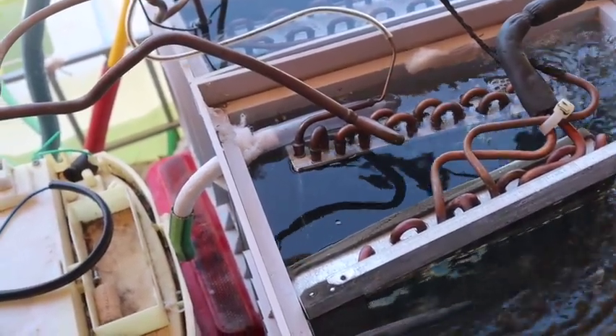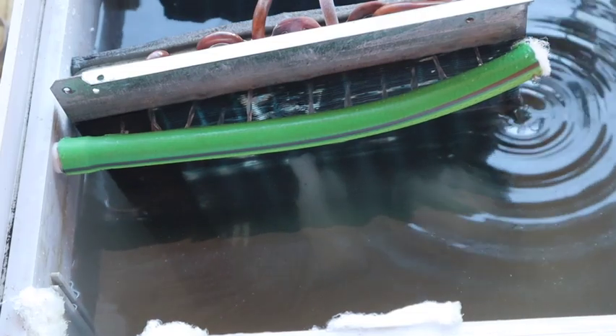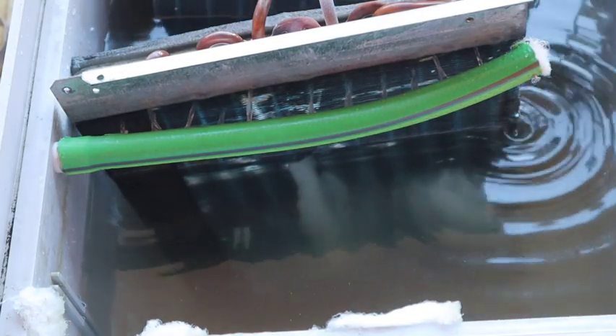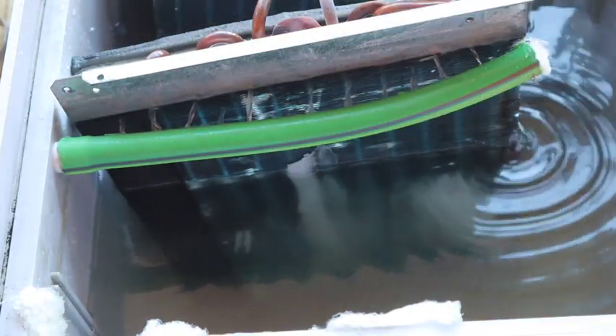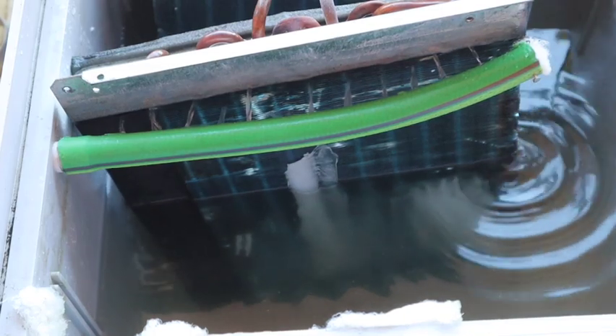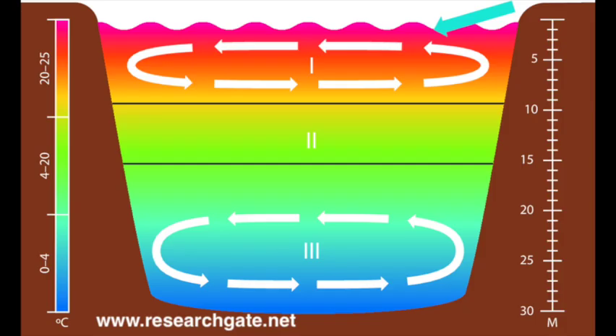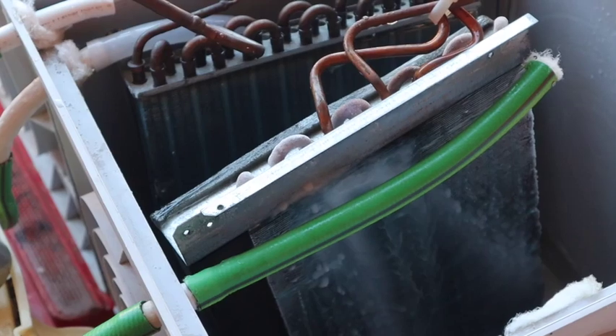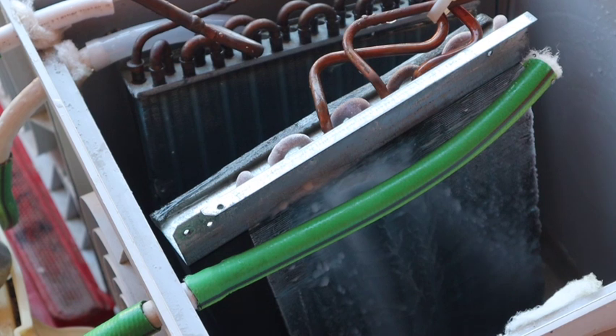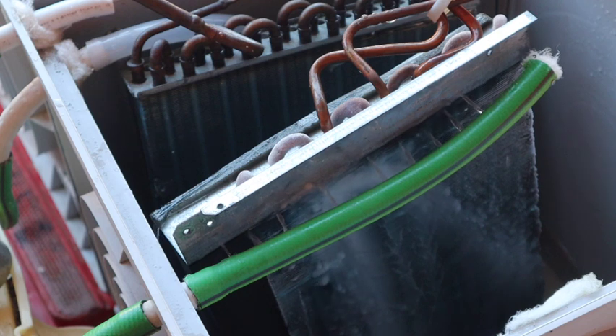However, it may be a good idea to close the false air hole, emptying the water box and install a linear shower on the evaporator to avoid ice formation. Stratification in a big cold tank will keep its surface relatively warm, so that if you return the water from there to the water box with the pump, you will have a higher temperature at the heat pump's evaporator. It will avoid ice formation, especially with the linear shower, and work with a better COP.